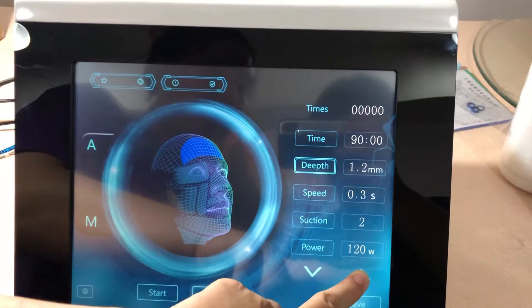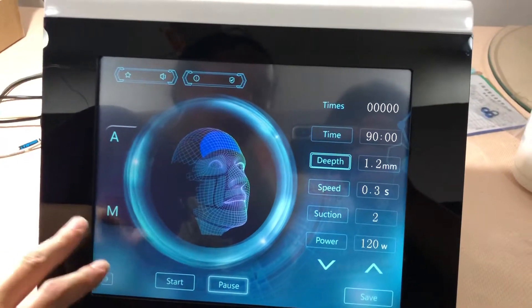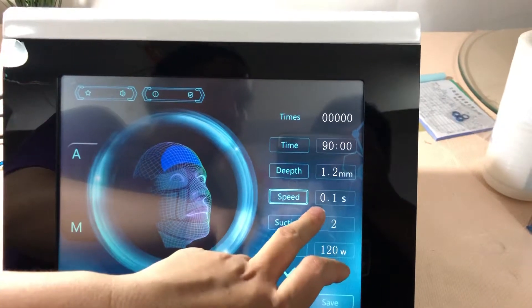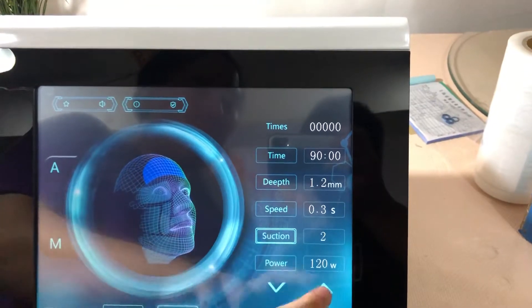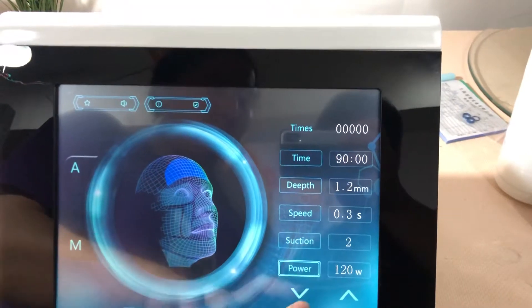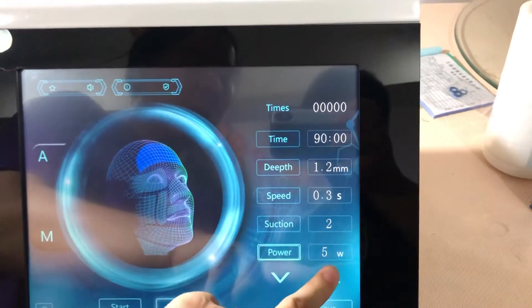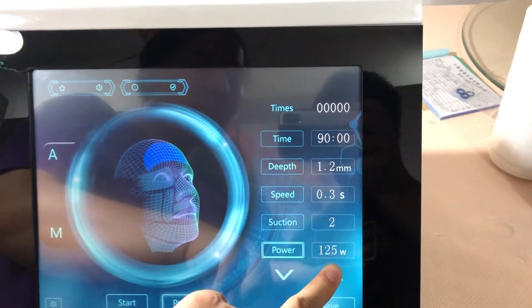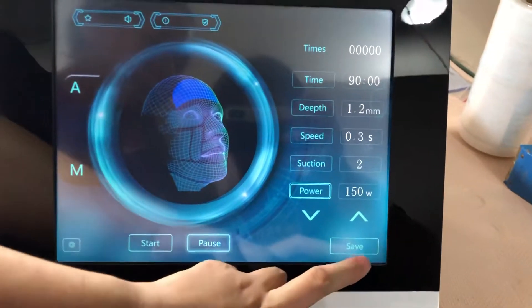This is Mode A. The maximum depth is 1.2 millimeters. For speed, the minimum is 0.1 seconds and the maximum is 0.3 seconds. Suction can be adjusted from none up to a maximum of 2, and power goes from zero to a maximum of 150.